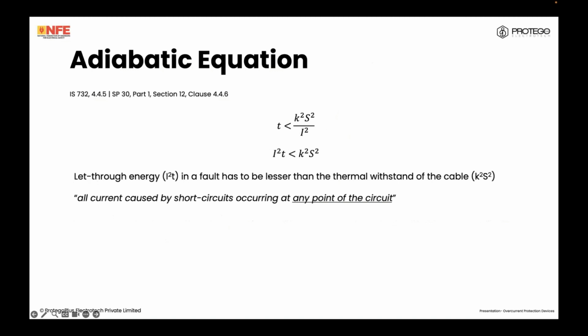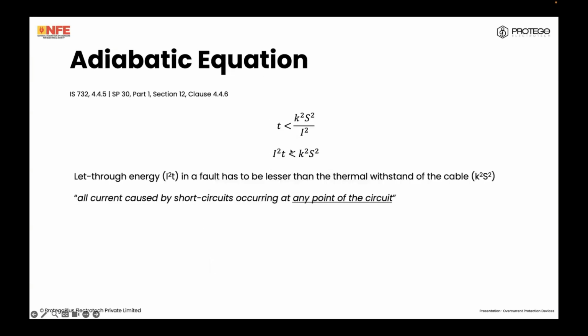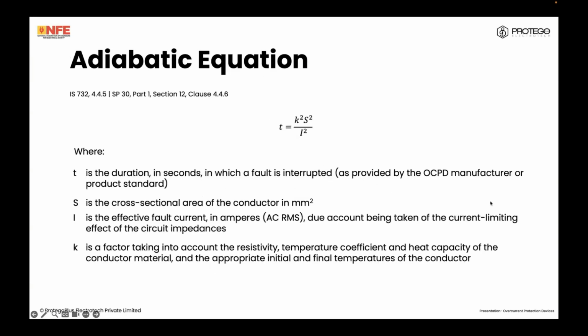The let-through energy in a fault has to be lesser than the thermal withstand of the cable. K squared S squared can be calculated. I'll show you how. And this has to be done for all current caused by short circuits occurring at any point of the circuit. So, I squared T, taking due account of the current limiting effect, is given by the manufacturer. They will tell you, for a certain amount of prospective fault current, this is the let-through energy. And this is given for the full range of prospective fault currents.